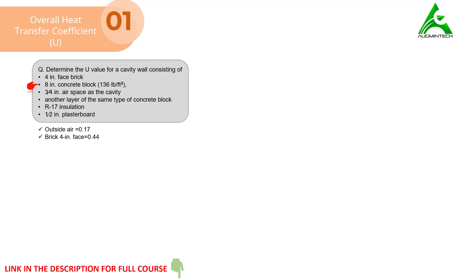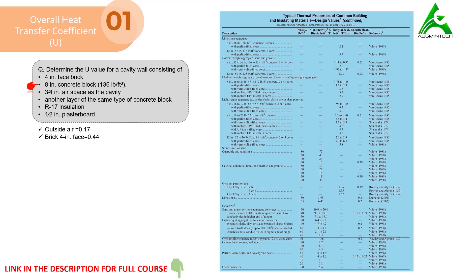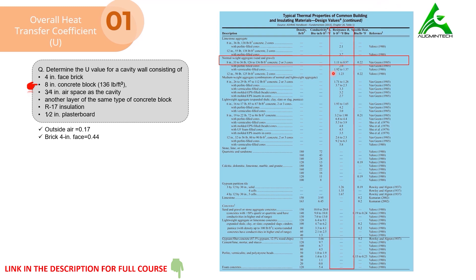Next we find the resistance of the 8-inch concrete block. We use the same chart, following the row for aggregate normal weight. Selecting the suitable row and column for resistance, the value can be taken anywhere between 1.11 and 0.97. So the concrete block 8-inch has the resistance of 1.11.